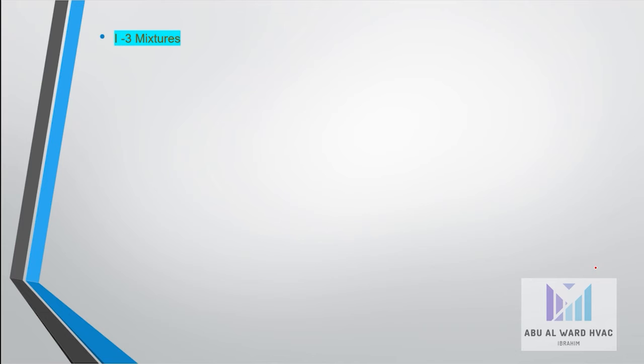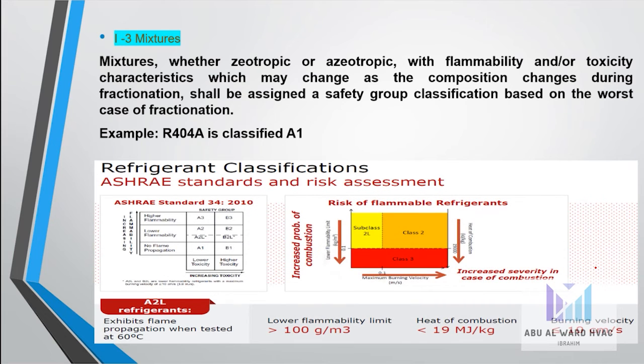For mixtures, whether zeotropic or azeotropic, those with flammability and/or toxicity characteristics that may change as the composition changes during fractionation shall be assigned a safety group classification based on the worst case of fractionation.